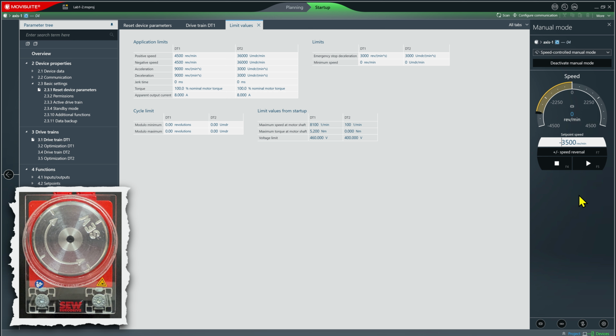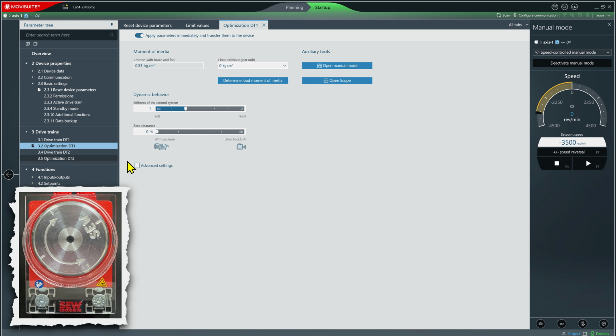Now we need to tune the VFD so that it can control the load properly. Now in my case, I happen to have nothing but a flywheel attached to my motor, which is not a very challenging load, but we can still tune it. Of course, in a real application, it would be much more interesting, but we'll do our best with our flywheel. So we're going to go back to the Drivetrains menu and pick Optimization DT1. This allows us to tune our drive.